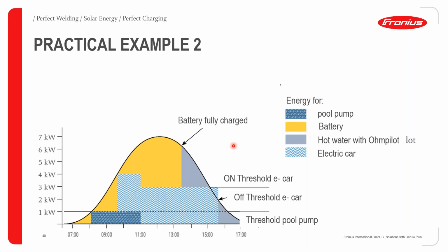In this next slide, we have the total PV generation for the day optimally used. The same thing applies as the previous slide, but here, at the usual time when the threshold for the pool pump is reached, it turns on and off at the same allocated time. In this case, EV charging has been integrated, with a threshold of 3 kilowatts - once reached, the car starts charging while the battery is also being charged. By about 2 p.m., the battery is fully charged, and the rest of the power surplus is used to generate hot water. So the whole PV generation for the day has been optimally used.